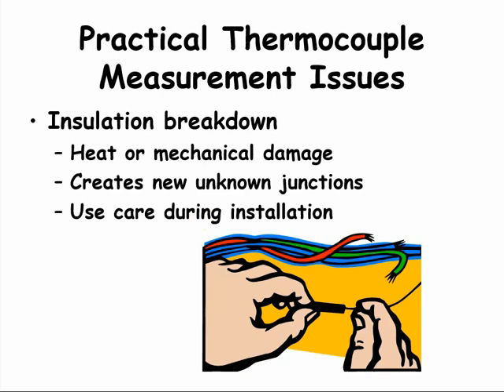Another measurement problem can be insulation breakdown with thermocouple wires and signal wires. If the insulation breaks because of heat damage or mechanical damage, the wires can touch each other and create new junctions. And hopefully you remember that thermocouple wire junctions of these dissimilar metals will create an EMF dependent on the temperature of the junction. So, if you have thermocouple wire that has extra junctions in uncontrolled areas, you will get erroneous readings. The best way to mitigate this is to use care during installation. This would be considered a bias or systematic error that would be hard to find, but careful calibration might help indicate that you have some extra uncontrolled junctions.